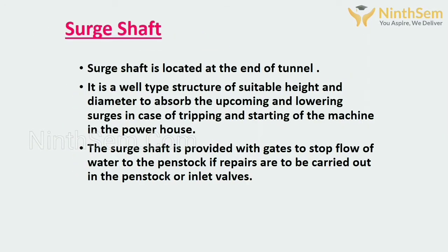Surge shaft. The surge shaft is located at the end of the tunnel. It is a well-type structure of suitable height and diameter to absorb the upcoming and lowering surges in the case of tripping and starting of machines in the powerhouse. The surge shaft is provided with gates to stop the flow of water to the penstock if repairs are to be carried out in the penstock or the inlet valve.